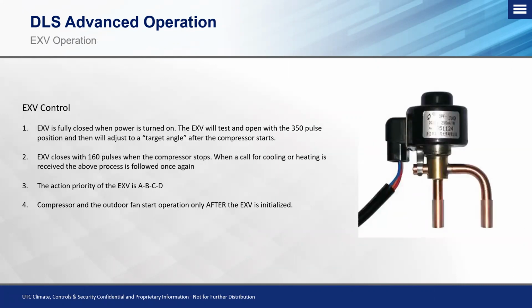All right, so let's jump over to the EXV operation. The EXV control is going to be fully closed when the power is turned on. The EXV will go through a test function and will open the valve with 350 pulses. On the multi-zone, this starts from port A and works its way up to 4, of course, depending on what model of multi-zone that you have.